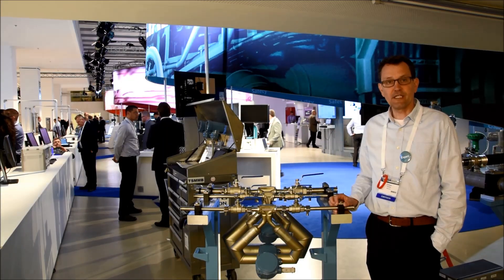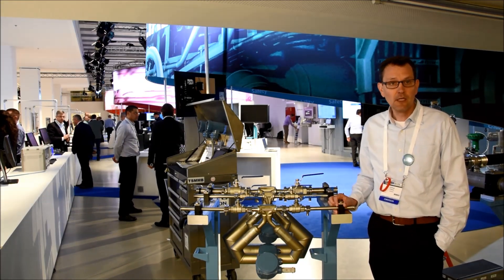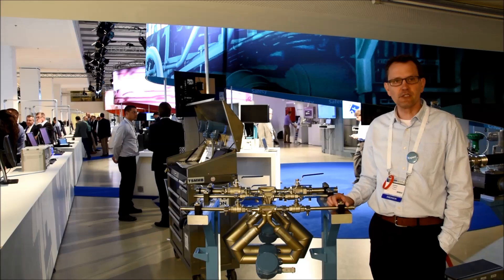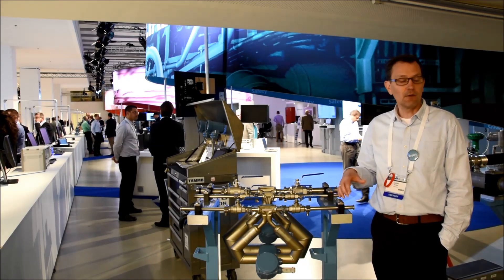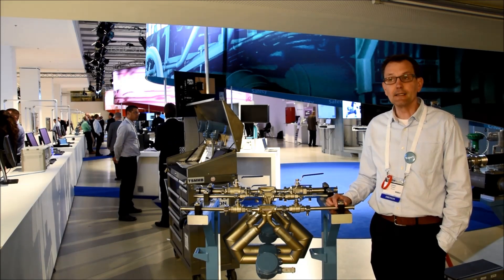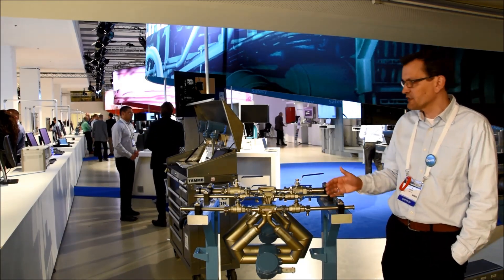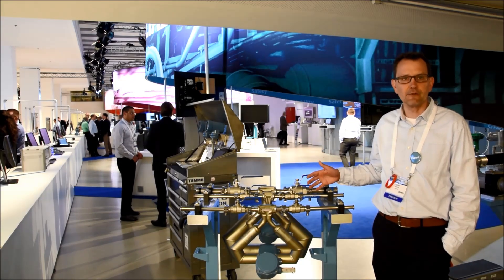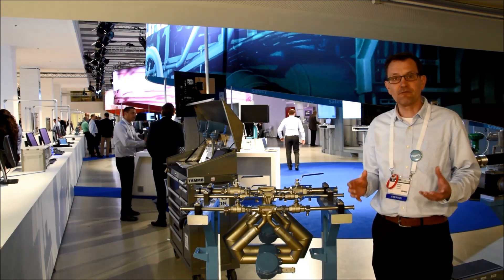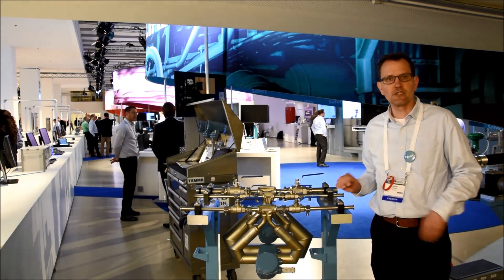Our mobile calibration rig has a set of highly calibrated, specifically selected master meters, which are calibrated according to ISO 17025. All our master meters have an accuracy of 0.05 percent, and with the whole setup using water fluid, it guarantees you an accuracy of 0.075 percent. We have master meters ranging from CMF 300 down to CMF 0.025, covering calibrations from 1.8 kilogram per minute up to 600 kilogram per minute.